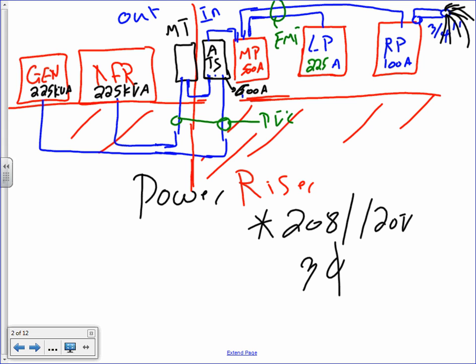On the outside of the wall, that one here is a meter terminal. Because we're higher than a 400 amp or 200 amp, you have to terminate into a CT cabinet. Meter terminal box, CT cabinet. Because we're higher than 200 amp, they bring the conductors into a CT cabinet, current transformers, to measure. And right in here, as a matter of fact, I don't know how we're going to do that in Revit, but it's going to be a meter here. Can you see that right to the top of it? It's going to be a meter. That's how you measure the current. Can I move on from the riser?